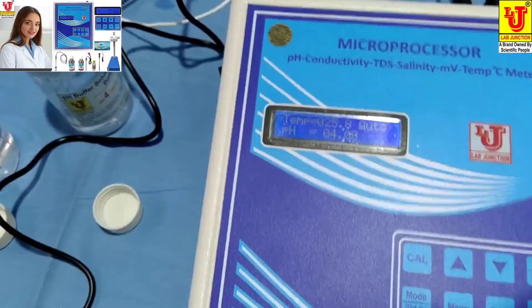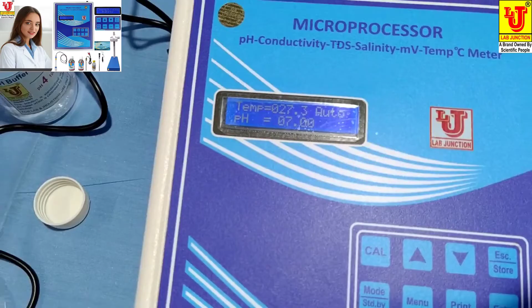And now I am changing this to another sample, just like 7 pH. Rinse this this way. Insert in 7 pH. Directly 7 shows. Now I am calibrating conductivity. Now I have to select from this key. Press for parameters, press enter. This is pH. This is ORP. This is conductivity, press enter. Now conductivity is auto selected. Now this is the conductivity solution, 1.000.